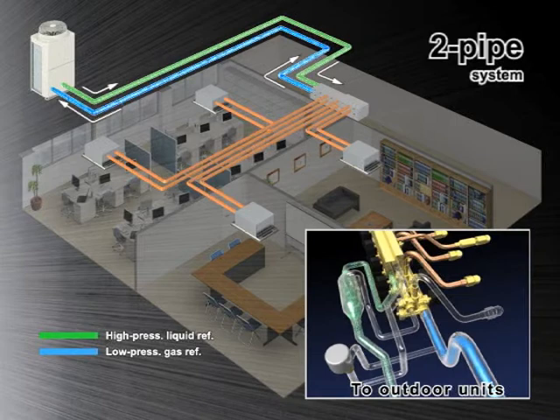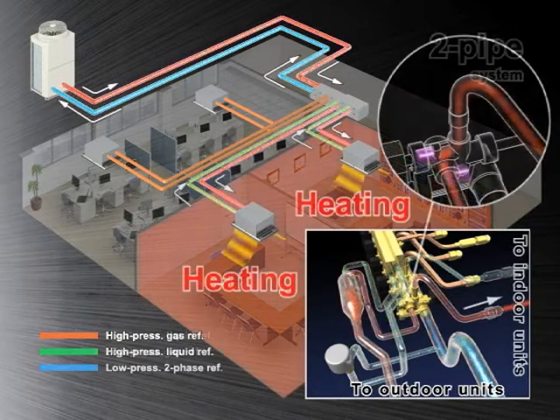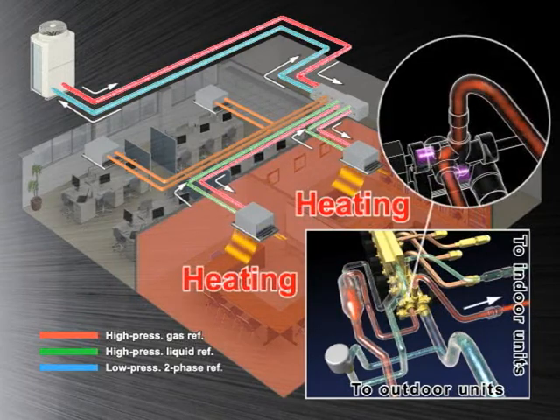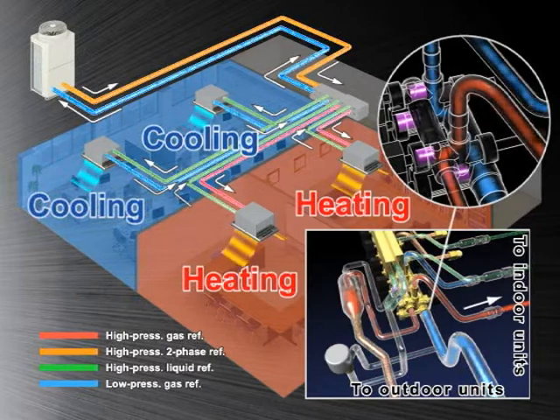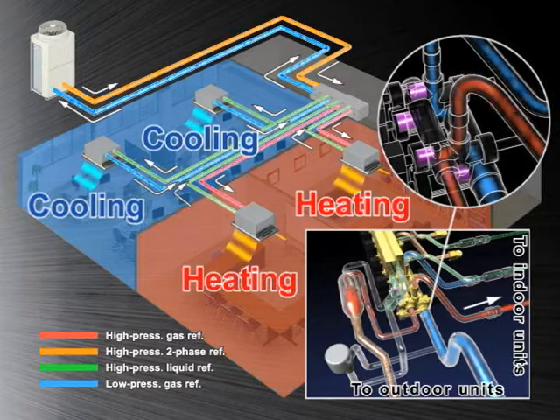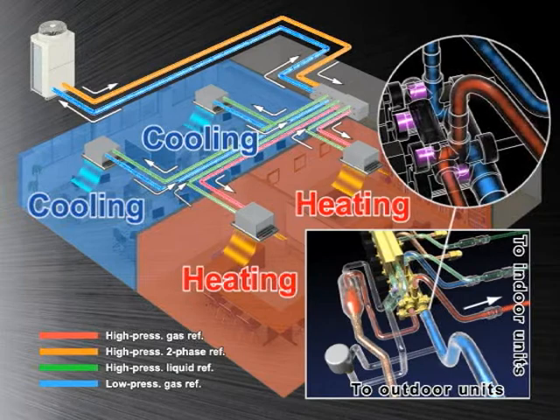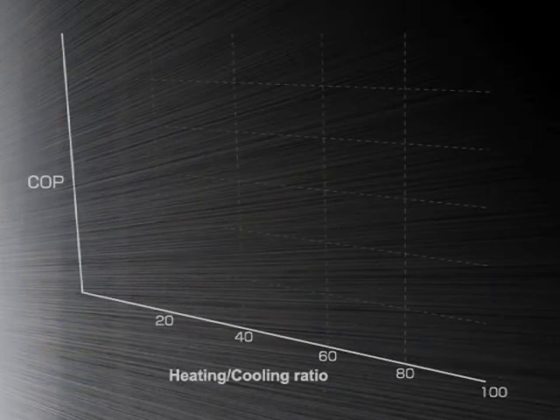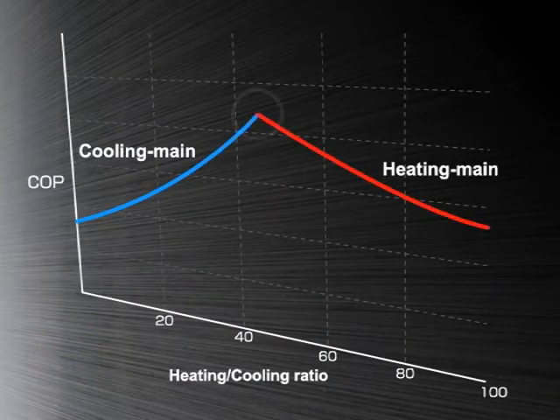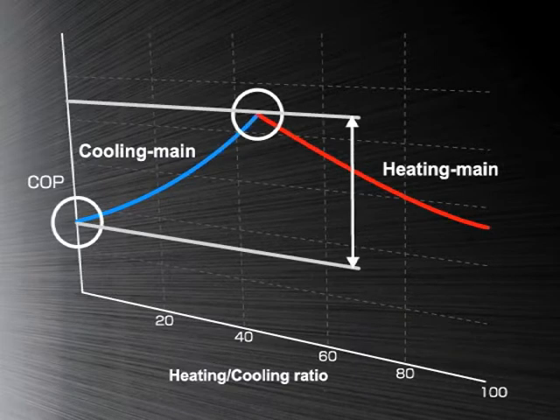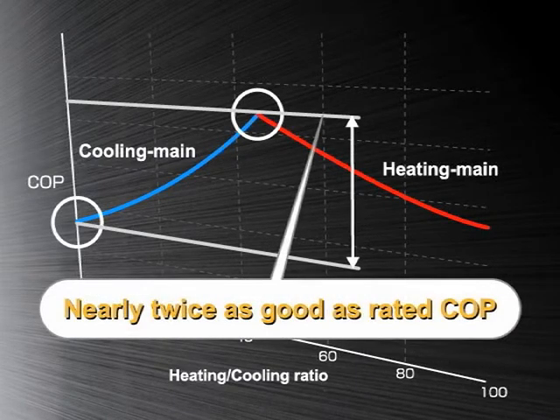An LEV, or linear expansion valve, delivers appropriately phased inputs to each indoor unit, depending on the individual heating or cooling requirements. In heating mode, gas refrigerant is delivered to the indoor units. If heating and cooling are required in the same system, the LEV switches the refrigerant flow. The gas refrigerant delivered to the indoor units in heating mode circulates back as condensed liquid refrigerant and is then delivered to the indoor units in cooling mode. In this way, the more frequently cooling and heating operations are simultaneously carried out, the higher the energy savings from reusing waste heat.